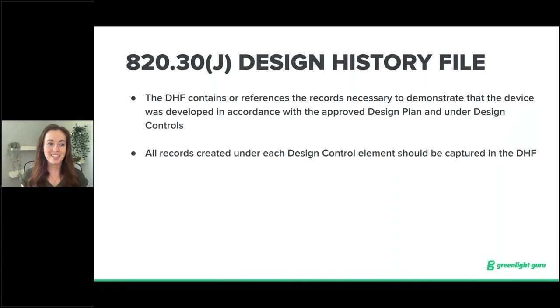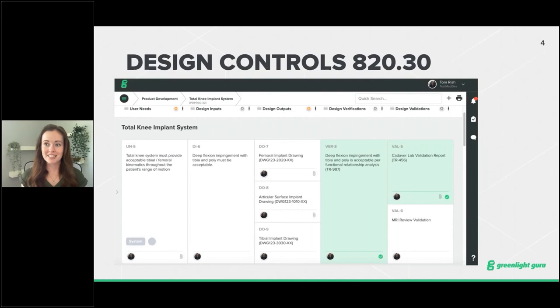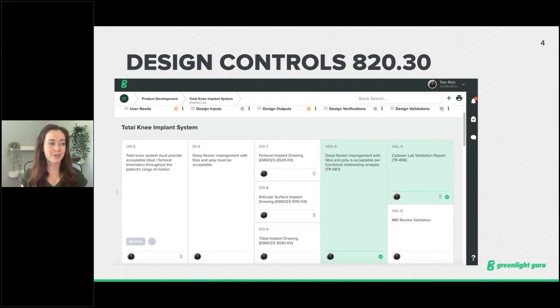On traceability — the screen shows a design control matrix for a total knee implant system built within Greenlight Guru. Until manufacturers move to an EQMS with this functionality, the traceability matrix is typically maintained through an Excel file. This shows a direct correlation between design inputs to verifications, outputs back to inputs, and user needs to validations. Ultimately, the goal of your traceability is to tell the story of your design — for example, from the user need to fit appropriate ranges of motion all the way through to the MRI review validation in the cadaver lab study.